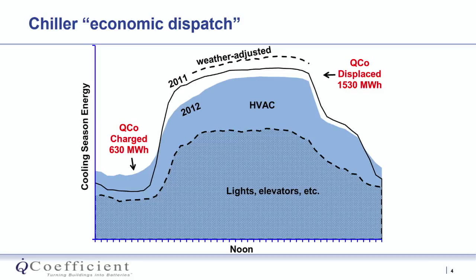At night I'm charging, because running your air conditioner at night is more efficient than running it in the middle of a hot summer afternoon. In these buildings I have multiple chillers, so I get to pick the most efficient chiller to operate at night, and then control what point on the chiller efficiency curve I run it at. So I have a lot of choices at night.